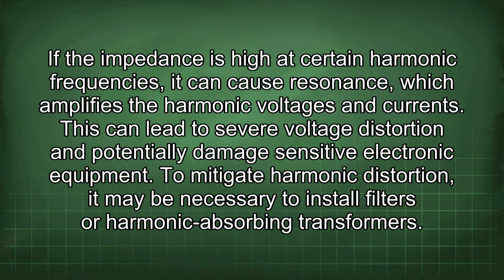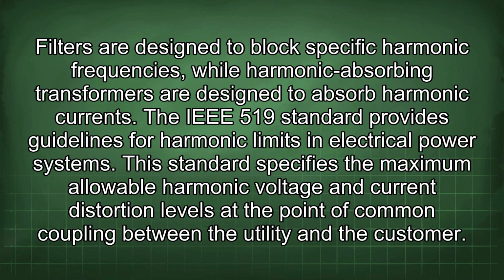If the impedance is high at certain harmonic frequencies, it can cause resonance, which amplifies the harmonic voltages and currents. This can lead to severe voltage distortion and potentially damage sensitive electronic equipment. To mitigate harmonic distortion, it may be necessary to install filters or harmonic absorbing transformers. Filters are designed to block specific harmonic frequencies, while harmonic absorbing transformers are designed to absorb harmonic currents.